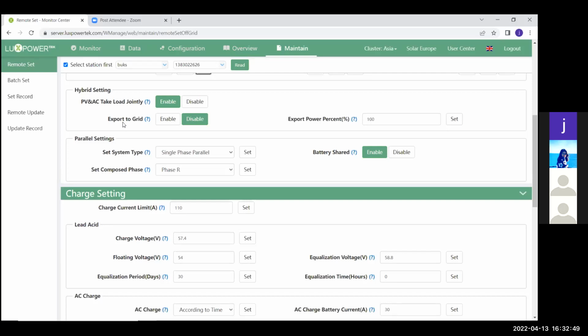This inverter also has the capability to backfeed. If you want an inverter that can backfeed into the grid, this inverter can backfeed. Now, at this moment, I've disabled the backfeeding function. This guy doesn't want his inverter to backfeed at all, so he has disabled it.